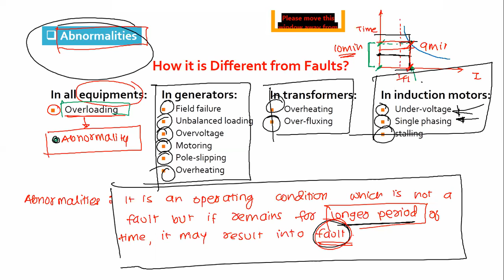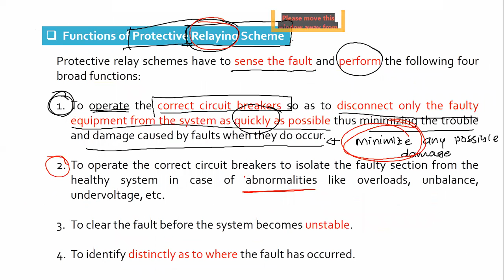Second is to operate the correct circuit breaker to isolate the faulty section from the healthy section. In case of abnormality also, because we have seen that an abnormality, if it remains for a longer period of time, may result in a fault. Suppose there is an overload, and I'm just giving an example, that a motor would take this much overload for 10 minutes. So we should design a relay so that if this overload remains for 9 minutes, we trip the motor, because we don't want to exceed beyond 9 minutes. This overload may result in a fault, failure of insulation, and the relay must also be able to operate in case of abnormalities that remain for a longer period of time, like overload, unbalanced voltage, and under voltage.